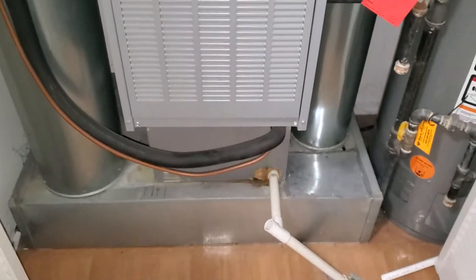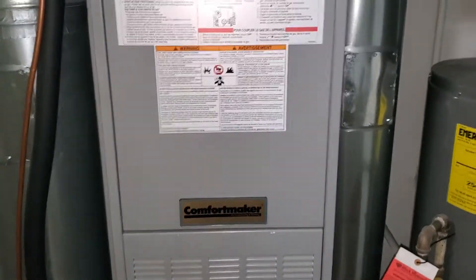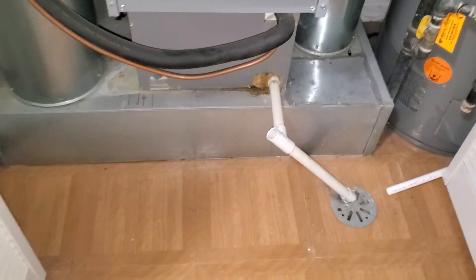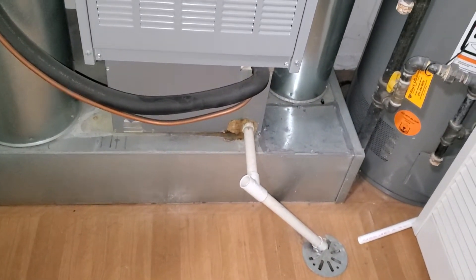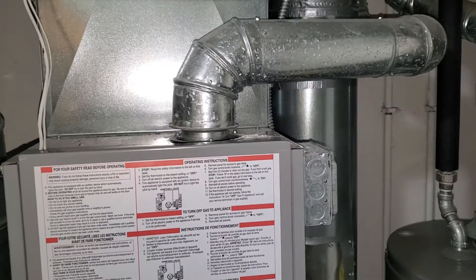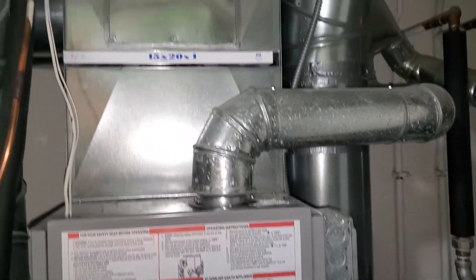We are working with 15 and a half inches. Our coil is actually 15 and a half by 20. Our return is going to be a 16 by 19. Our filter is a 16 by 20 by 1.